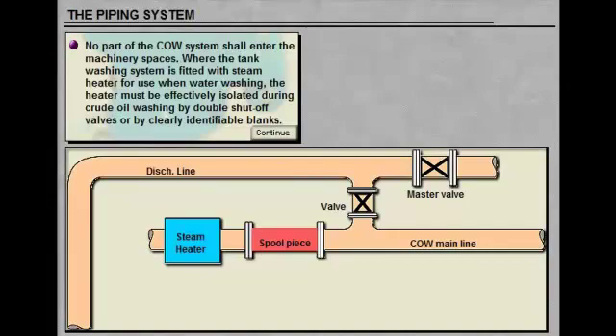No part of the crude oil washing system shall enter the machinery spaces. Where the tank washing system is fitted with steam heater for use when water washing, the heater must be effectively isolated during crude oil washing by double shut off valves or by clearly identifiable blanks.